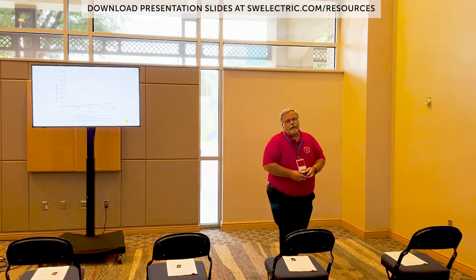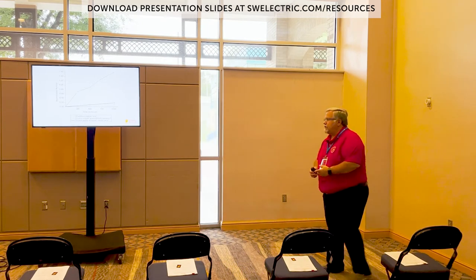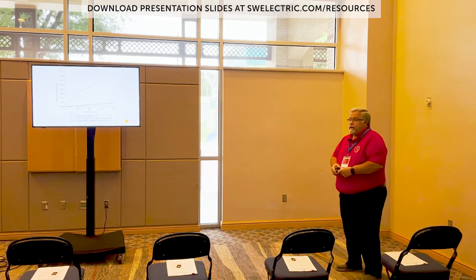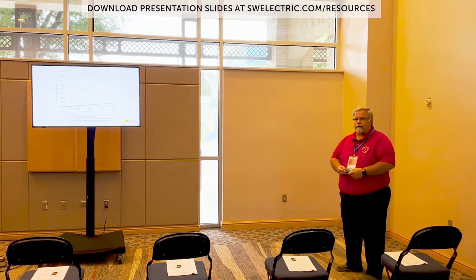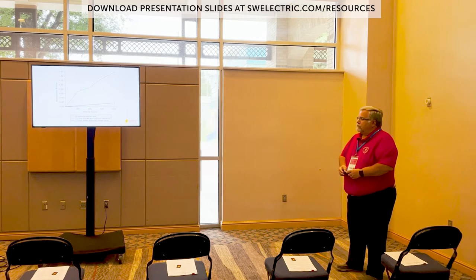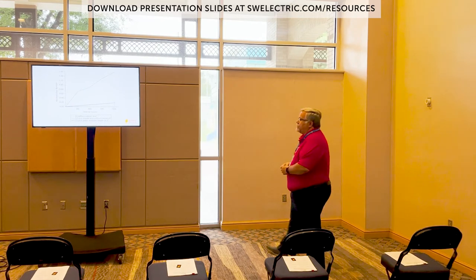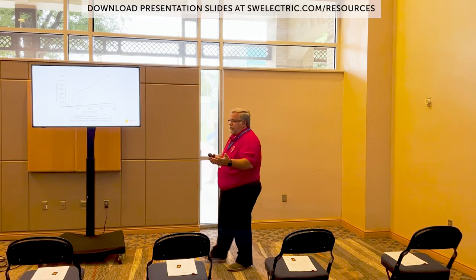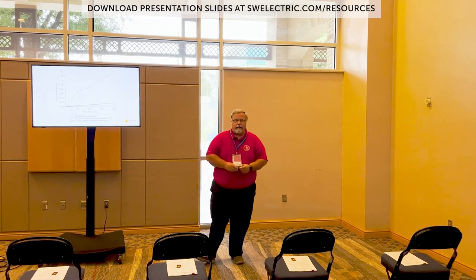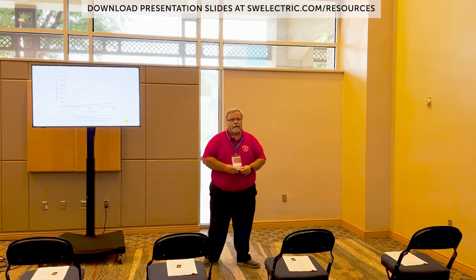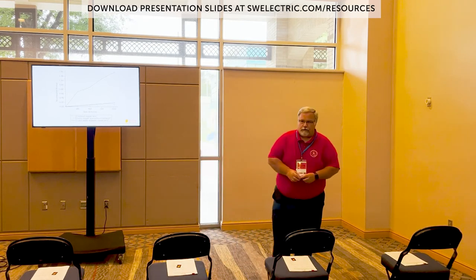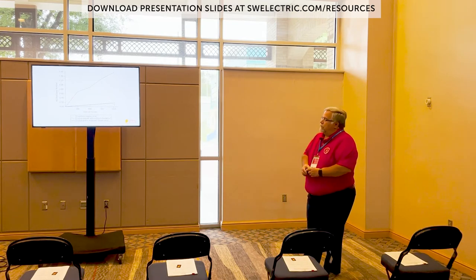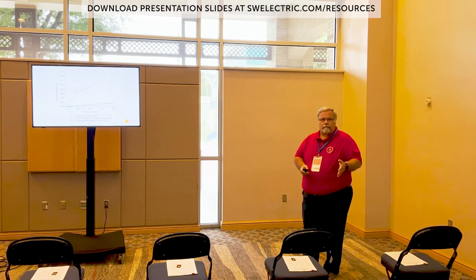That's why it's so important to do annual oil testing. Oil testing is probably one of the, or it is without a doubt, the cheapest thing you can do on an energized transformer. But if we have a bad gas test or whatever that might be, we might want to take the time to de-energize the transformer, isolate it, and do an electrical test on it to confirm it. We're all about confirming. All these tests should trend.